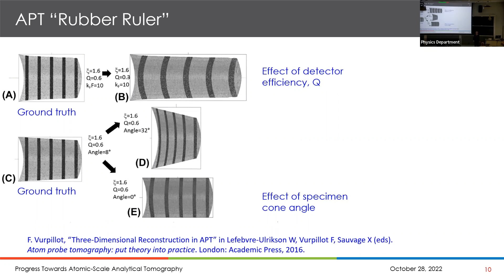But if you do everything correct, except you get the detector efficiency wrong, what you can see here is you get a different result, right? And in fact, not only is it expanded in Z, but these flat features are now curved, all right? So this is a rubber ruler. There's another illustration. If you don't know the cone angle of the specimen, but you say, well, it's about 5 degrees, you can make some kind of guess, 8 degrees. Or if you put a large one, you can see the change of the reconstructed volume, say for a 32 degree versus, in this case, a 0 degree. So this is the effect of cone angle on the resultant image. And the bottom line is that this is not an acceptable outcome for imaging. We need high spatial fidelity.